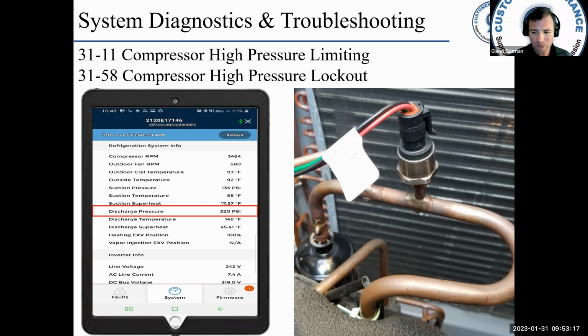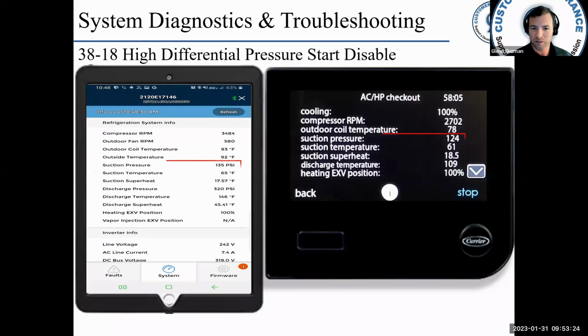But again, it goes back to what is the unit seeing compared to what you see with your gauges. Okay. 3818 is a high differential pressure start disable. This is an interesting code. I've seen this happen maybe once or twice. When the compressor is attempting to start against high pressure, it can result in start failures. The pressure equalizing valve is included to ensure the compressor will never start against high pressure differential. The fault will become active if a demand exists and the PEV is not successful in lowering the pressure differential below 100 PSI. All right.